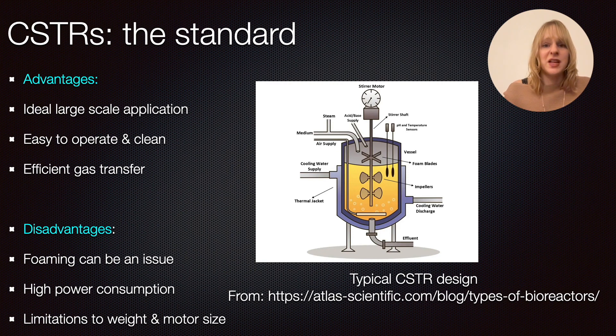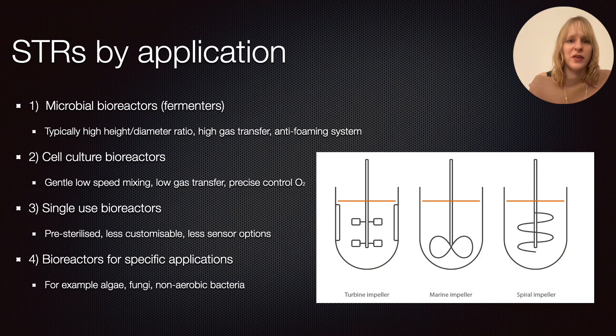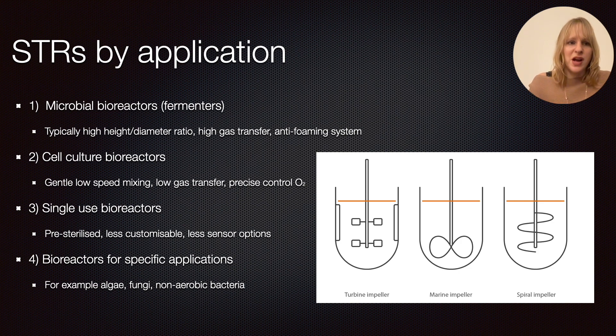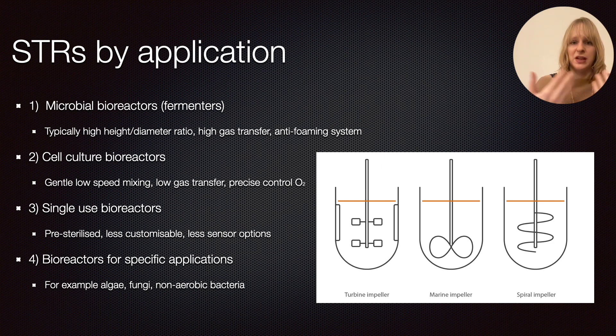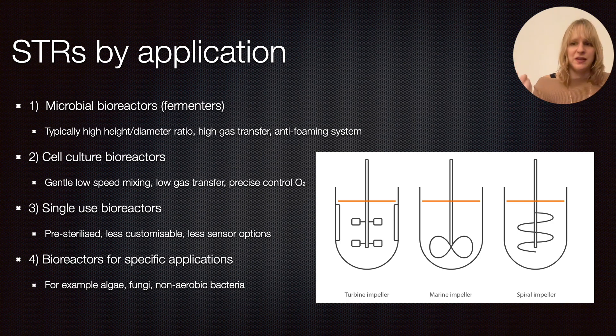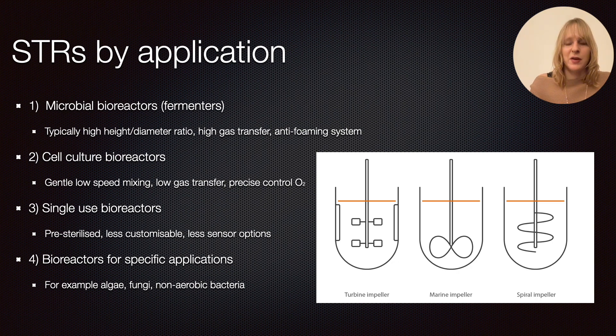Looking at types of stirred tank reactors broken down by application, the first two relate to what type of microorganism you're working with. For a microbial bioreactor or fermenter, you typically have a very high height-to-diameter ratio because that allows more efficient gas transfer, and the anti-foaming system becomes really important. Different impellers are associated with this — some generate much higher shear to facilitate high gas transfer, while others like the marine impeller need less energy input for gentle mixing, making them more suitable for gentle cell culture systems that can't tolerate high shear.